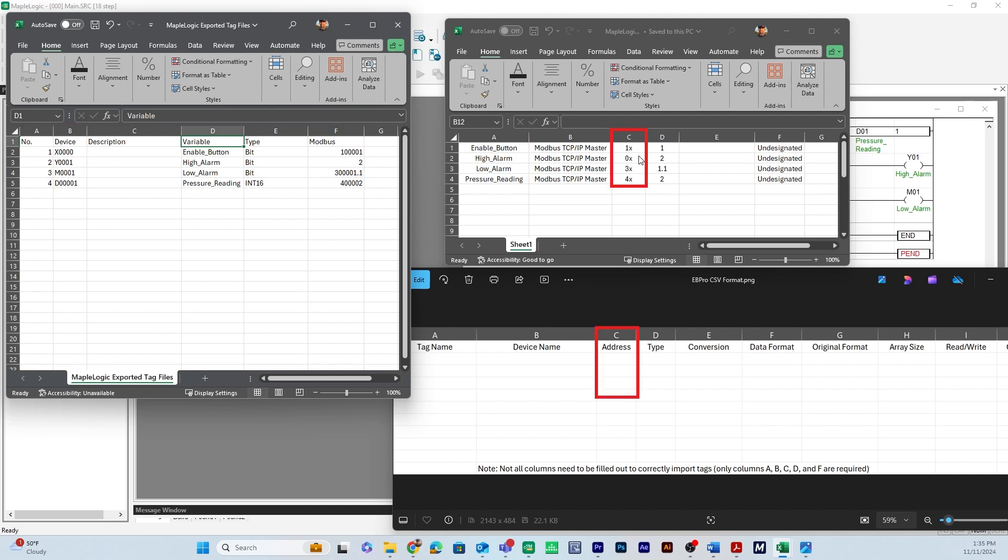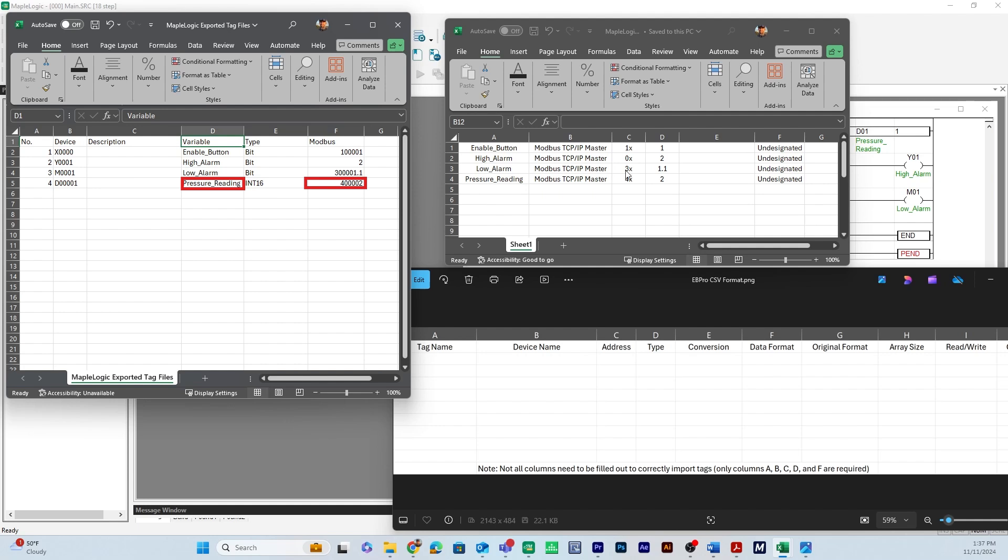Column C is going to be address. It looks different here for our actual type and address and you can notice that for example pressure reading is 4-0-0-0-0-2 when it's exported from Maple Logic. We will need to change it to 4x2 when importing into EB Pro. This is how EB Pro reads that address.